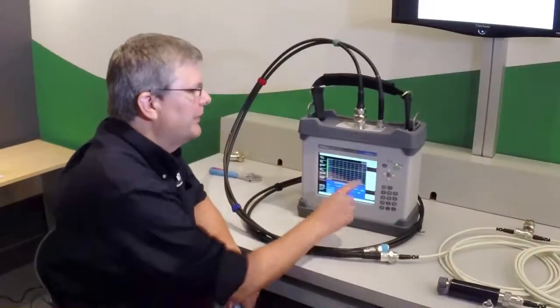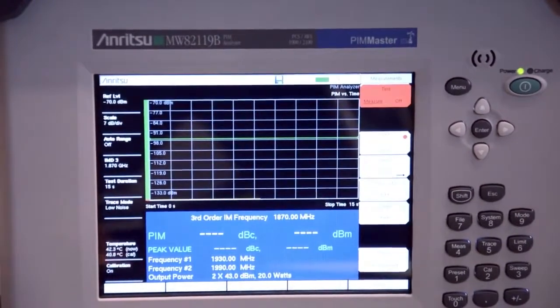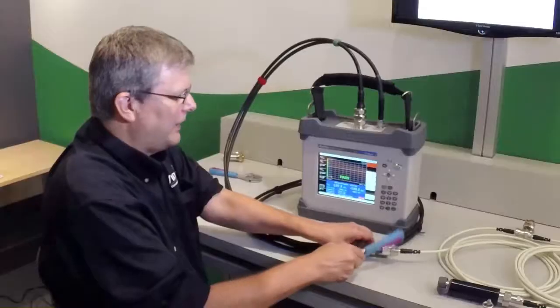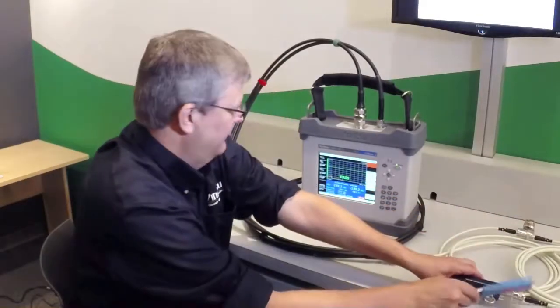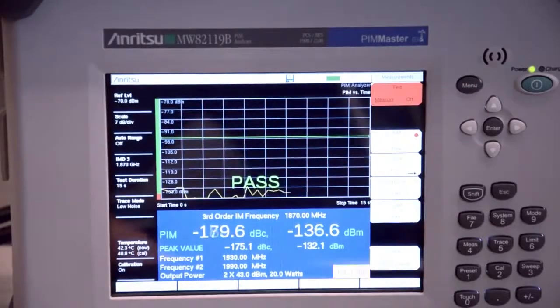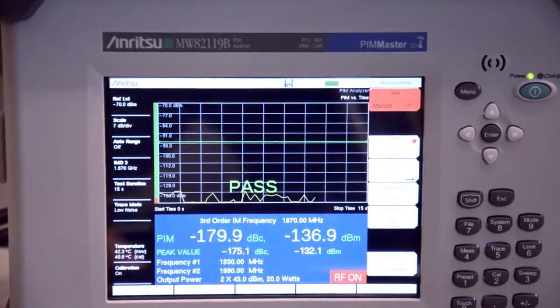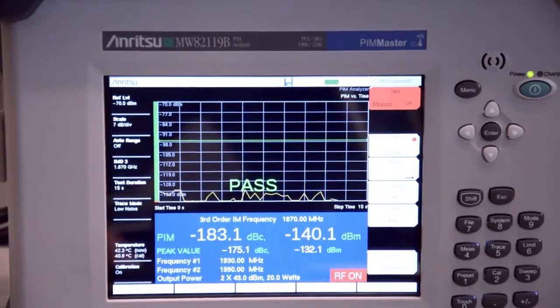So now that I've completed my PIM repair, I do my final PIM versus time measurement, while tapping on the connections. We now see that we have a stable PIM measurement even when applying the dynamic testing. This is now a passing result.